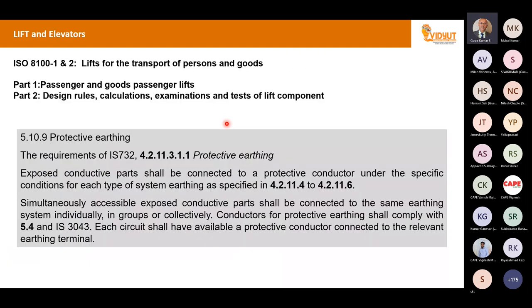But now the situation is changing. The new BIS is about to publish a new lift standard based on ISO 8100 parts 1 and 2. If we look at the earthing requirement for lifts, in high-rise buildings a lot of electrical inspectorates ask for two separate run-off strips going to two separate earth pits, causing a lot of confusion. But in the new standard, what is written is protective earthing: you should do earthing as per IS 732, have protective equipment, and connect the exposed conductive parts of the lift to the protective equipotential bonding of the installation.